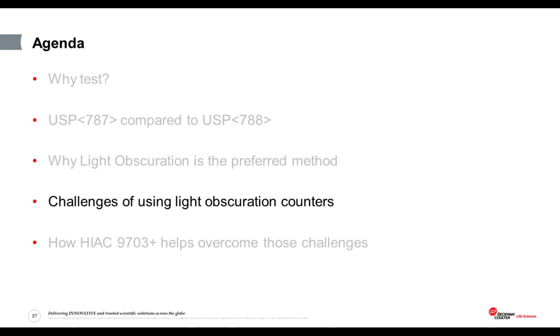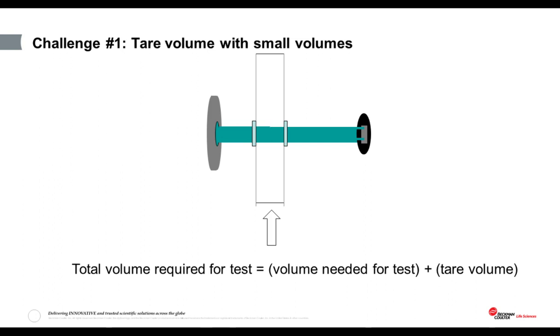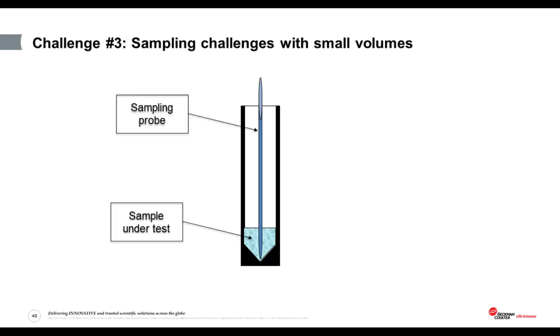Okay, so now you can understand why the USP prefers the use of light obscuration counters for these tests. However, there are some challenges of using this technology to fully achieve the benefits of testing to USP 787. So let's take a look at some of those. Now, as stated earlier, provided the counter is capable of precision counting in volumes as small as 0.2 of a milliliter, the whole test could be done on a vial containing enough for 4 samples plus the tare volume of the counter. Now, the tare volume is the volume of the sample pathway leading from the vial to the obscuration counting windows. In many general purpose counters, this tare volume is large enough to prevent the test being achieved with just 1 milliliter.